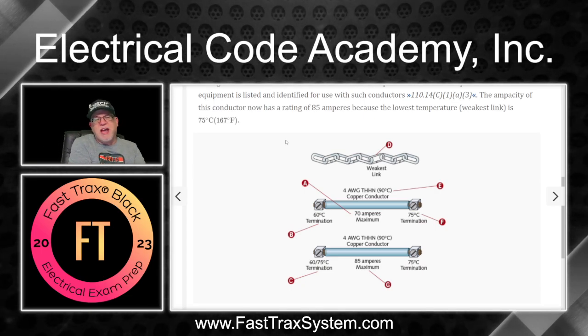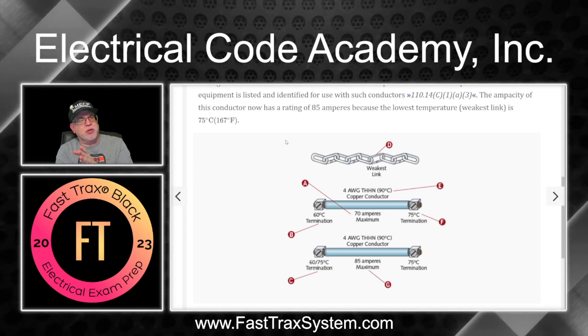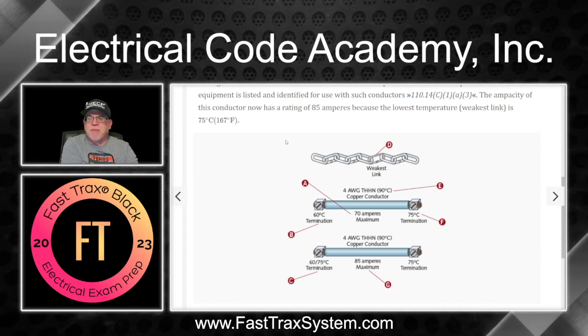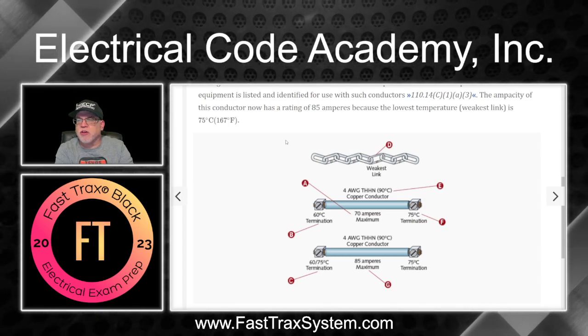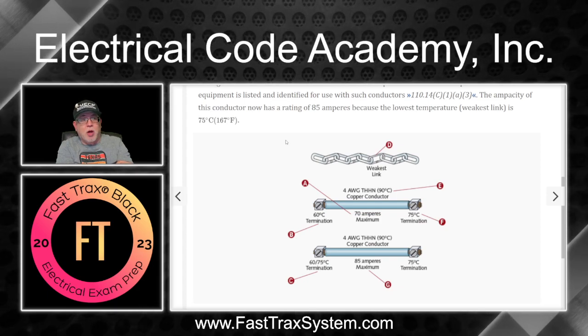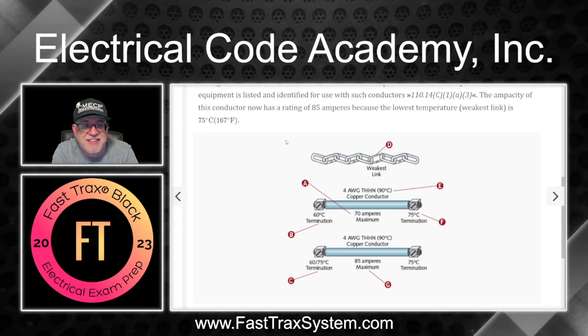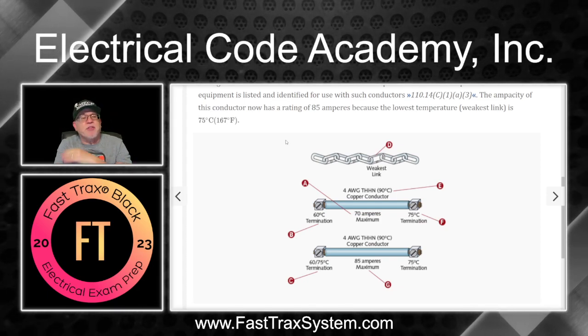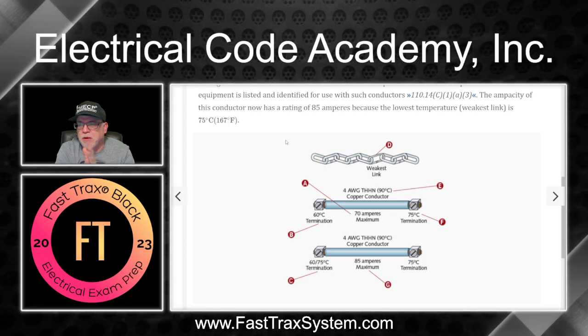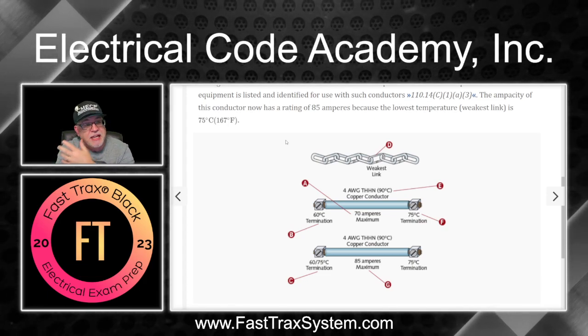So this is what you do every day in the field and you don't realize you're doing it. You're running MC cable, for example, and you know that it's under 100 amperes, and somebody comes along and tells you that it's got to be limited to 60 degrees. But the 60-degree ampacity table, which is 70 amps if it was a 4-gauge, in the NEC.